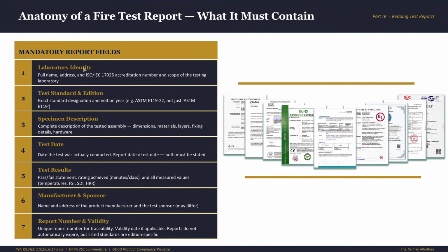First, the laboratory identity, test standard and edition, specimen description, test date, test result, manufacturer and sponsor, and report number and validity. Starting with laboratory identity. I need to know the name, the address, the accreditation number, and scope of the laboratory. And the scope must list specifically the test method and edition. For example, a lab accredited for EN1363-1 cannot automatically do EN1363-2. The scope covers the exact same testing standard and year.